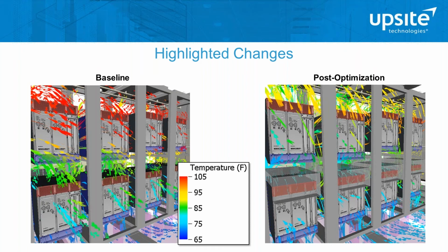But what's possible, as you're demonstrating here, is that by making improvements to how the air is managed in the room, you're able to reduce temperatures in the first place, get rid of some hot spots, giving you room to raise supply temperatures and realize those efficiency improvements without, in the end case, causing higher intake temperatures to the IT equipment. And in some cases, they're actually lower. The hot spots have gone away, and you've raised supply temperatures. So it's really important to have that conversation at that level to break out the different components.